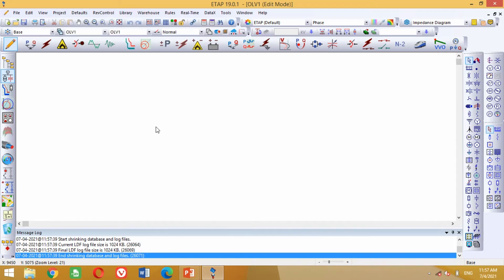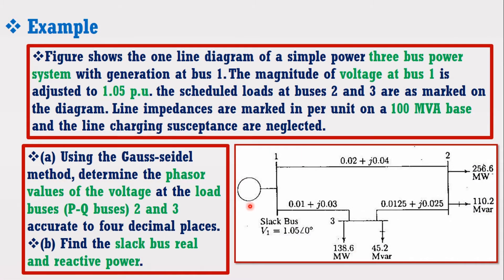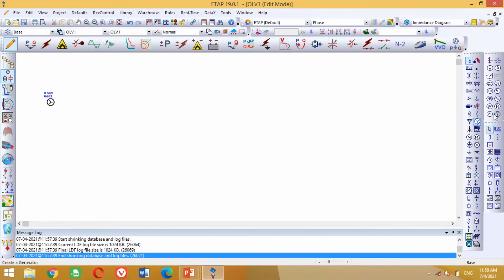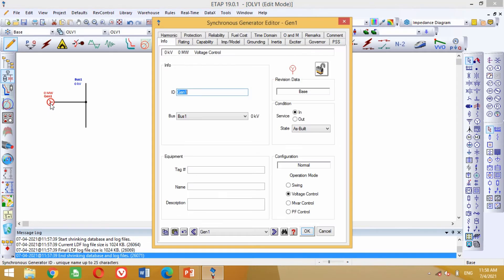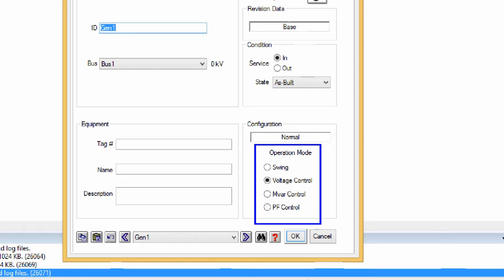To design the load flow analysis, look at the figure. At the first stage, we need a generator for the slack bus. The slack bus has the voltage of 1.05 per unit with phase angle of 0 degrees. Now come to the ETAP screen again. Bring the generator in the model from here and paste it anywhere on the screen. Click on this generator and press Ctrl+R to rotate it in your desired direction. Now bring the bus in the model, paste it here, and rotate it by pressing Ctrl+R. Connect this generator with bus 1. Double click on this generator block and make it a swing generator by clicking on Swing in the operation mode.